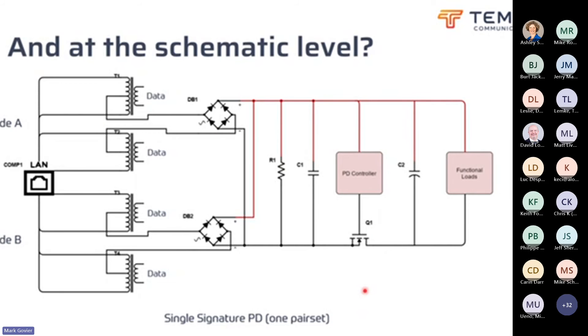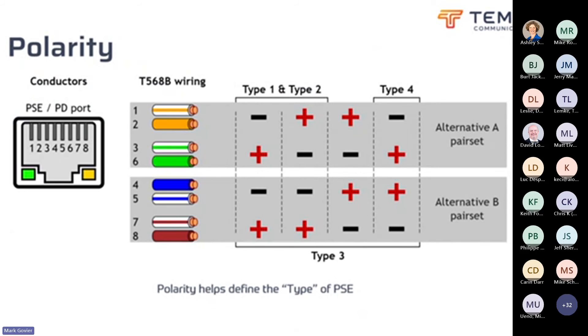Once the power sourcing equipment has detected that little bit of current flowing, it'll go through a hardware process to negotiate the power with the powered device. The powered device will actually pulse loads onto the current from the power sourcing equipment to indicate how much it wants. Up to that point, it can't take more than the basic amount — what we'll call class one. So looking at those various pair sets and how they're configured, we've also mentioned the term types and classes.